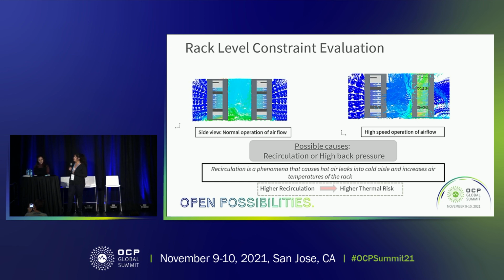What we have also seen in the simulation is that whenever there is a high power rack on one side and it's rear facing a low power rack, we would see that the high airflow consumed by the high power rack, which would be in the range of, say, 2,300 all the way to 3,500 CFM, if it's rear facing a low power rack, which would have airflow ranges between 600 to say 1,000 CFM, this is the type of airflow behavior we would see. The high velocity jets are almost overflowing into the back of the low power rack. So this can cause a couple of effects. One of them, obviously, there would be a lot of back pressure on the low power rack. The other one would be there could be recirculation. When I say recirculation, it means whenever there are these gaps and leakages between the racks or servers, and there is high pressure hot air there, it could leak through these gaps, mix with the cold air, and increase the inlet temperatures of these racks.